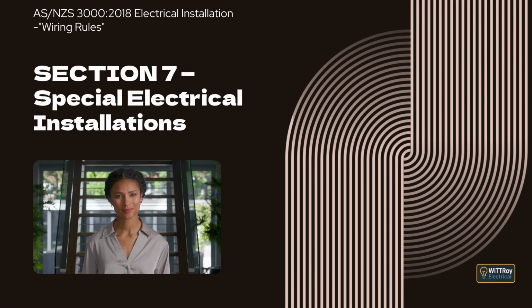Clause 7.2.6.3 Interposing switches for fire detection and alarm systems. This clause explains that no switch is permitted to be installed between a main switch and downstream switchboard supplying fire and smoke detection and fire alarm systems, so that supply cannot be accidentally interrupted. Clause 7.2.7 Air handling systems. This clause introduces air handling systems that are intended to exhaust and control the spread of fire and smoke, and confirms that these systems are treated as safety services.